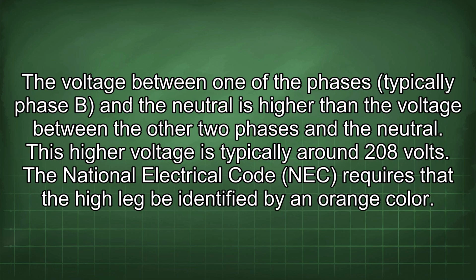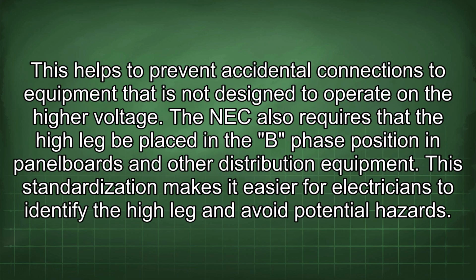The voltage between one of the phases, typically phase B, and the neutral is higher than the voltage between the other two phases and the neutral. This higher voltage is typically around 208 volts. The National Electrical Code (NEC) requires that the high leg be identified by an orange color. This helps to prevent accidental connections to equipment that is not designed to operate on the higher voltage.